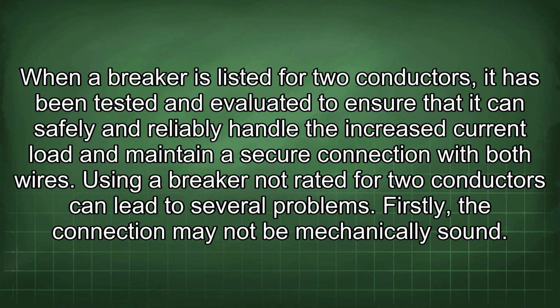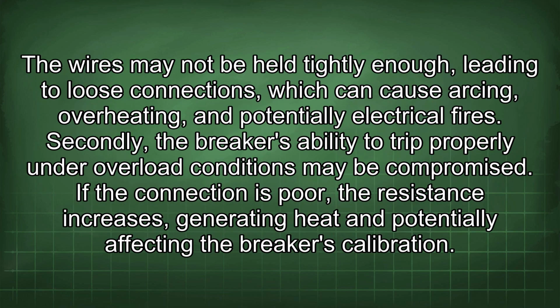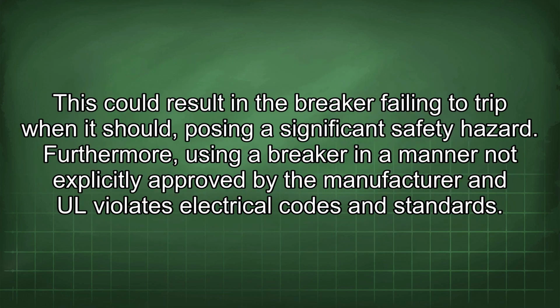When a breaker is listed for two conductors, it has been tested and evaluated to ensure that it can safely and reliably handle the increased current load and maintain a secure connection with both wires. Using a breaker not rated for two conductors can lead to several problems. Firstly, the connection may not be mechanically sound. The wires may not be held tightly enough, leading to loose connections, which can cause arcing, overheating, and potentially electrical fires. Secondly, the breaker's ability to trip properly under overload conditions may be compromised. If the connection is poor, the resistance increases, generating heat and potentially affecting the breaker's calibration. This could result in the breaker failing to trip when it should, posing a significant safety hazard.